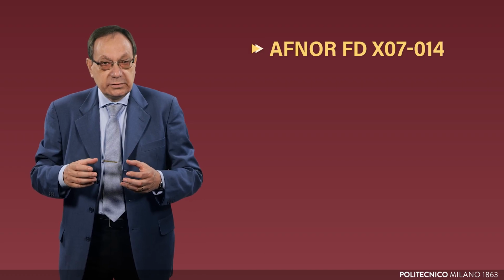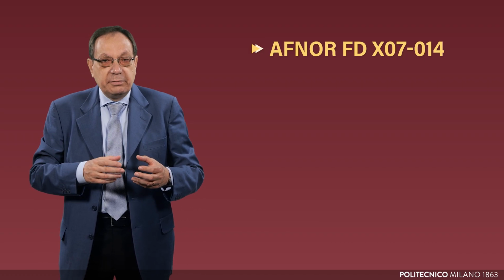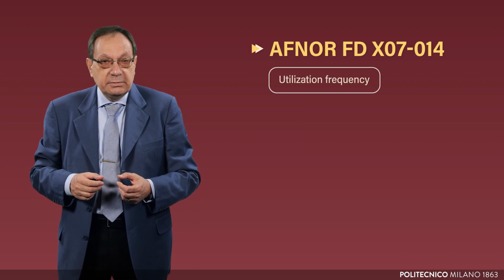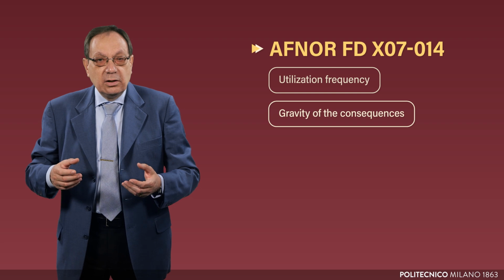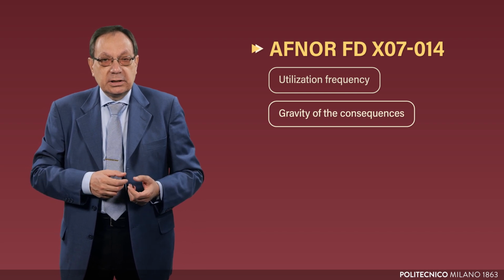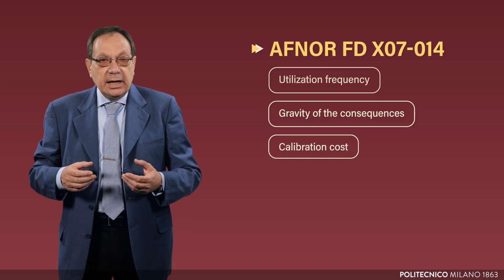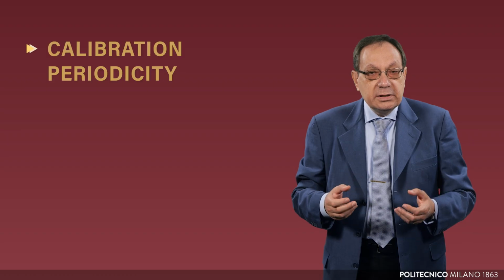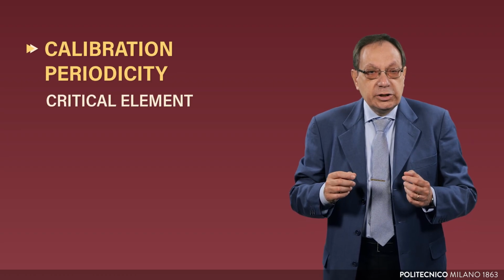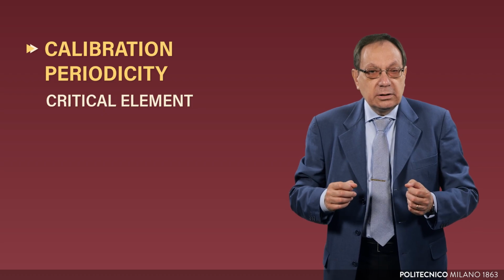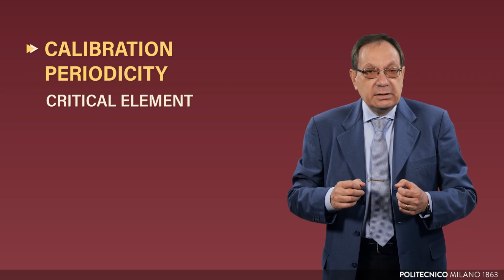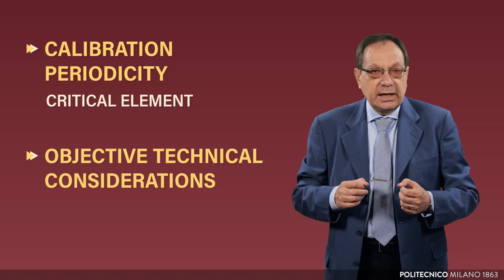What is shown here is a very simple method. There are others, such as the method considered by the French standard AFNOR FD X 07-014, which takes into account other parameters such as the frequency of use of the instrument, the seriousness of the consequences of failing to meet the required metrological requirements, the cost of calibration, and the tendency of the instrument to drift. The important aspect to consider is that the frequency of calibrations is a critical factor in ensuring the fulfillment of the required metrological requirements for the intended use, and must be established on the basis of objective technical criteria.